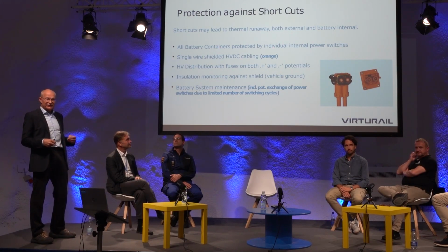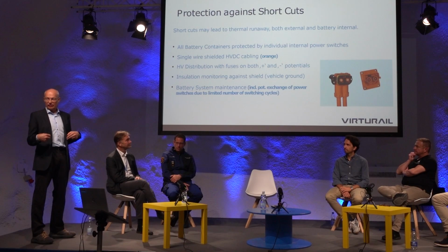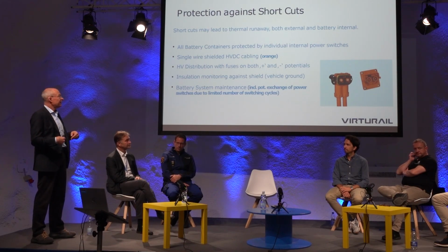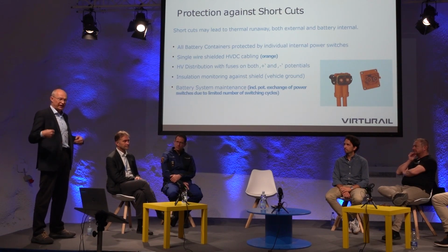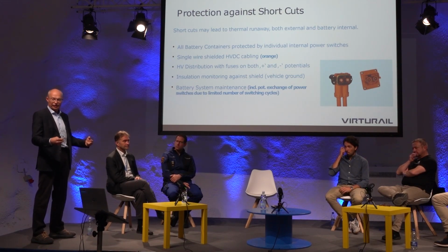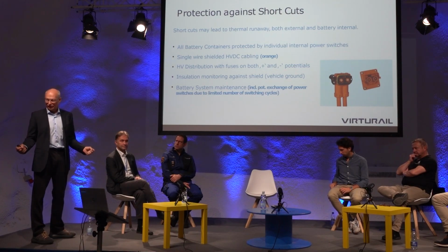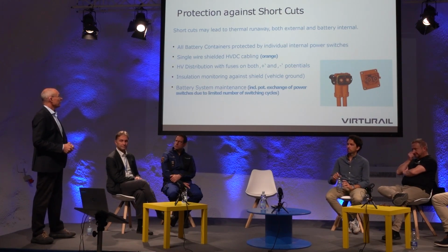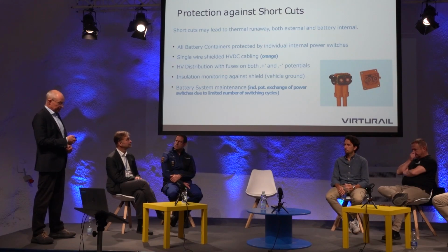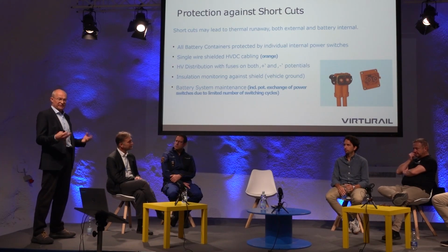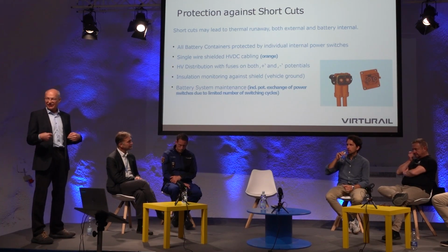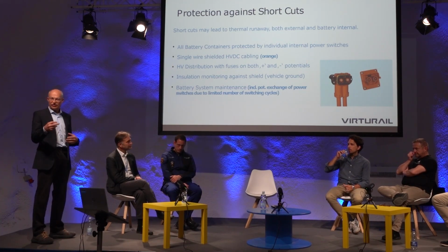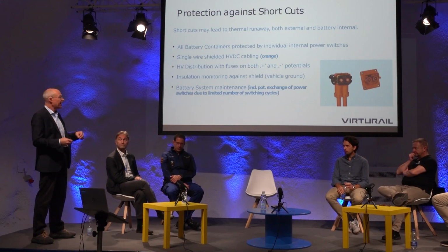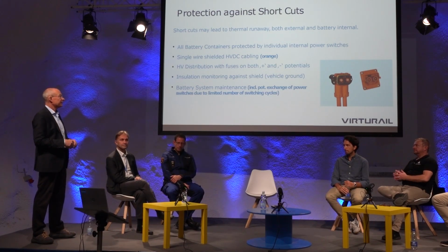The battery containers are first protected by internal power breakers. These power breakers need to be actuated by the battery management system, and in turn by the vehicle control system, in order to switch on the high voltage at all. For this, there's single wire shielded cabling, so there is an insulation supervision. As soon as there is an insulation fault between some lines and ground, everything is cut and operation is not allowed.